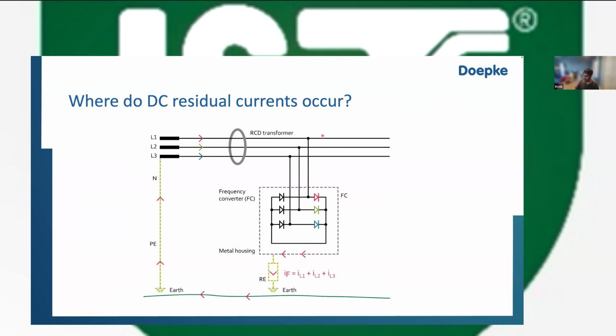I will explain. So let's just talk about a situation where we have an RCD protecting a three-phase rectification circuit, and then after this you may have a VFD, and we look at those specific cases. You may have the IGBT. But basically, in this situation, if you have a fault between any line and this DC bus, the overall fault current is the sum of what happens when the first phase peaks plus the second phase peaks plus the third phase peaks. So IF is equal to IL1 plus IL2 plus IL3.